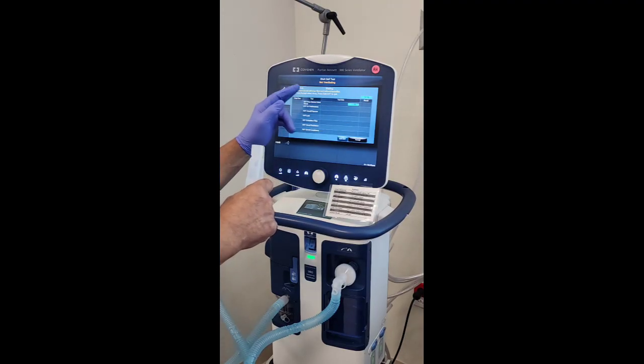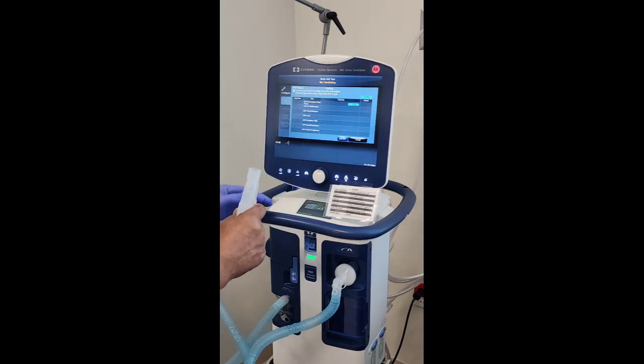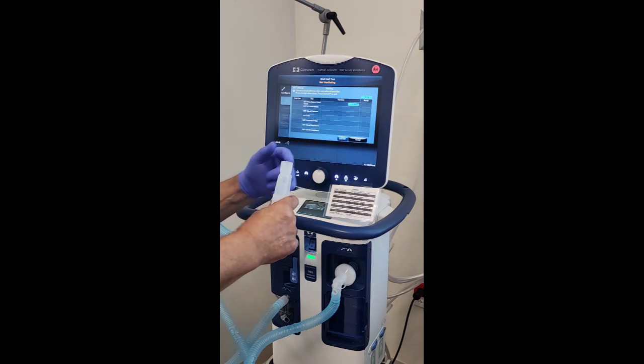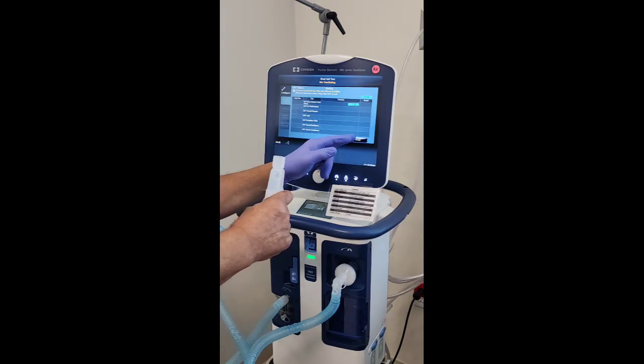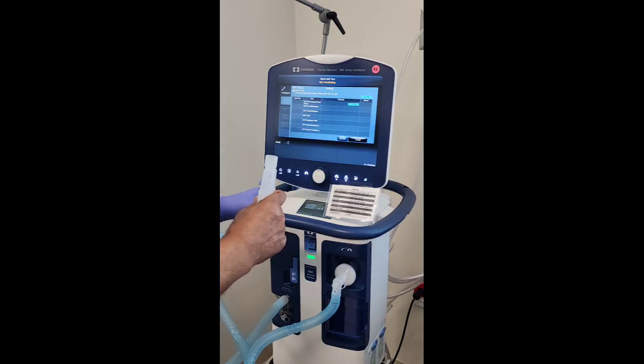It says connect circuit with inspiratory filter and without humidifier. Okay, so we're not connected to the humidifier. We have the inspiratory filter right here, the bacteria filter, and I'm ready. Just accept. Again, I'm not touching it. I'm keeping no resistance in front of this opening here. Accept. Checking the flow sensor right now.